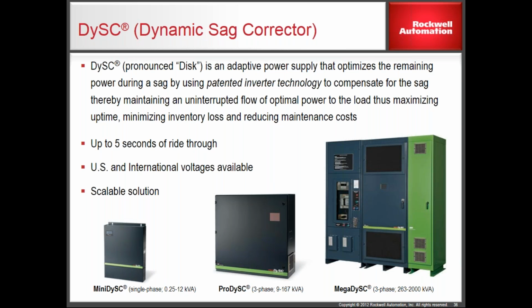These are bus level solutions. In this solution set, the inverter cabinet is here. The IGBTs are all in here. This cabinet here is switchgear. So at that level, it comes with auto bypass switchgear. It'll actually bypass itself if it had a problem without dropping your load. Right? It's designed - one of our biggest users in the world of this product is the semiconductor industry. And in their world, a downtime event's $1 million. They don't want it to go down. I don't care whose problem it is. If you got a problem, don't take me down. So this gear won't take them down.